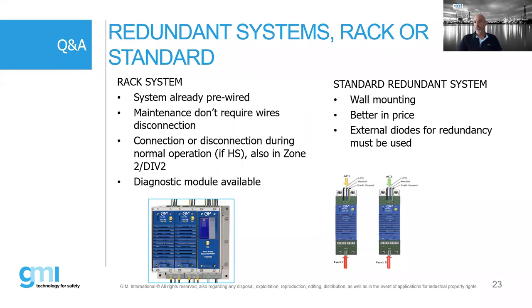Why use others' solutions on the market, the standard DIN rail power supplies? We have, of course, wall mounting or DIN rail mounting possibilities. Price is better, because some of you already asked about prices. Price is better, of course, because you don't pay for the rack. But you have some limitations. You don't have diagnostic, and you also need external diodes for normal power supplies, not ours. The normal power supplies in the DIN rail version need diodes for redundancy, and those diodes, as Massimo said in the previous slides, can be a critical point, sometimes a bottleneck. They consume energy and they can fail, as we sometimes see. So external diodes could also be a problem.